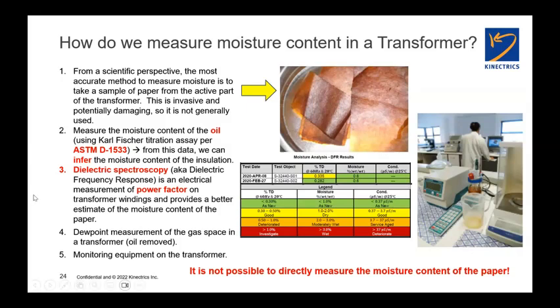Another technique that is used, and I don't know if Chris talked about that because I came in a little bit late into his presentation, is a newer test called dielectric spectroscopy, otherwise known as dielectric frequency response, which is a power factor measurement taken over a wide frequency band from about 0.1 millihertz to 1 kilohertz. The instrument that performs that measurement has a database built into it, and it will take the curve that results from that measurement and give you an estimate of the moisture content of the paper insulation inside the transformer, which is the colored chart that you see on the right-hand side. In this particular case, a Megger IDAX was used to take this measurement, and it comes back and says, here's your power factor, your dissipation factor, tan delta, and here's your associated estimated water content.